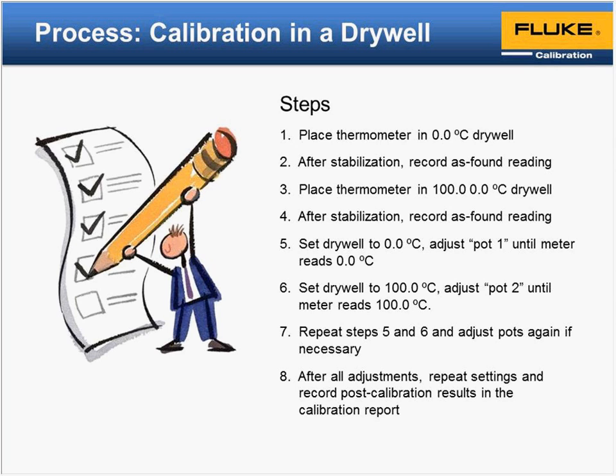So we would place the thermometer and probe in the well, set to 0. Allow the dry well to come down to temp and stabilize. You'd want to check the specs on this. Just because the display is now reading what you think it is, it's always good to allow maybe 5 to 10 minutes once you've reached temperature to let everything equilibrate. Then you take your as-found reading of the system, and then we simply set the dry well up to 100, come up to temp, stabilize again, and then we take the as-found reading there at 100 as well.